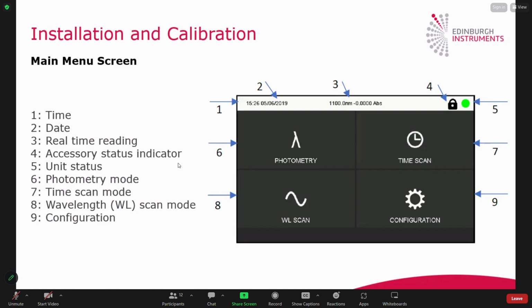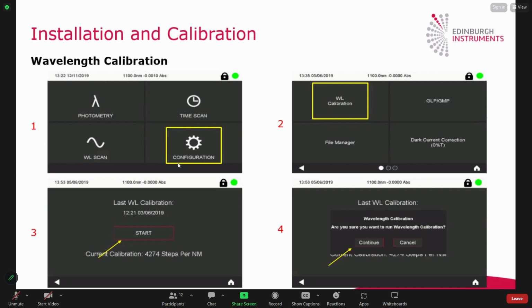And basically there are three major operation modes. On the left is the photometry and the wavelength scan, and on the right is the time scan and configurations. The configuration means the settings of this instrument. Before the measurements, you need to do some wavelength calibrations. First, you go into the configurations, and then you choose the wavelength calibration. Then you press the start button, and then you press continue to start the calibration. Then the machine will show the calibration in progress, and after you finish the wavelength calibration, the instrument will be healthy and available to use for the measurement.